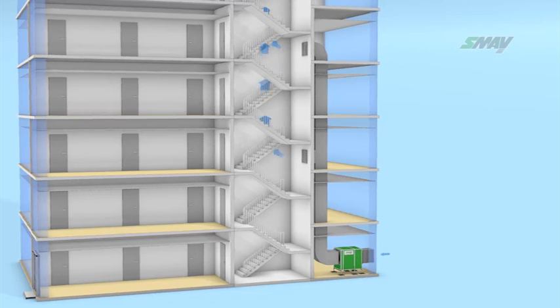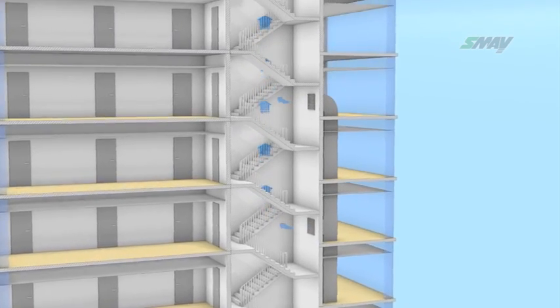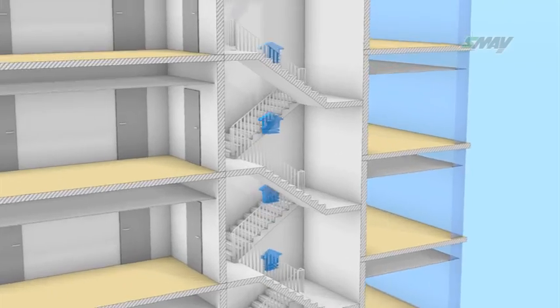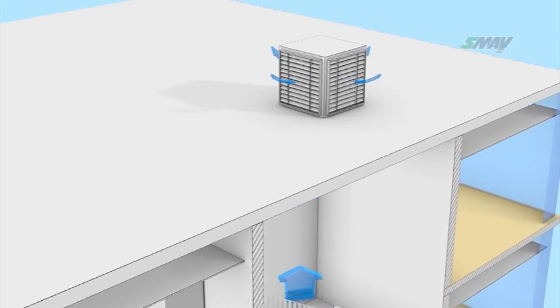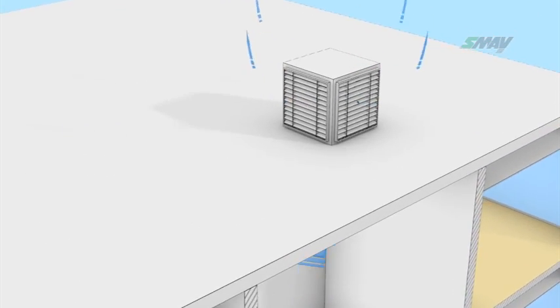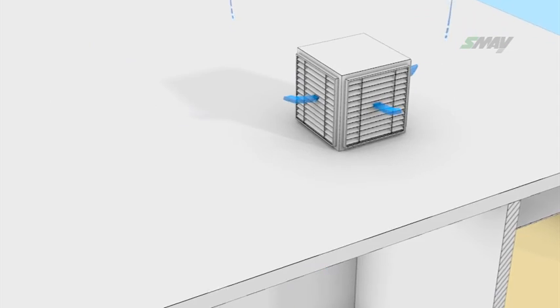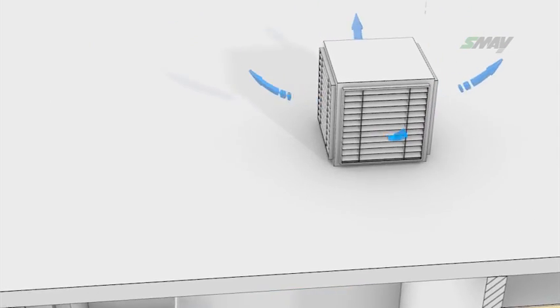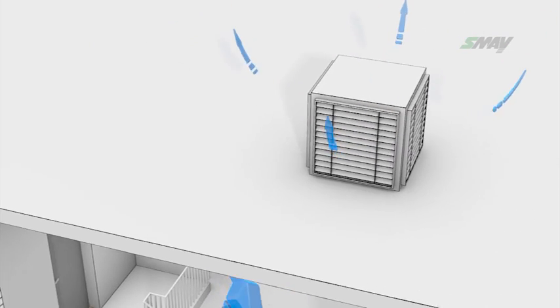In pressure differential systems designed with a long time delay from the fire detection moment to the activation of the system, it is recommended to provide an opening at the top of the staircase with an active area of 0.3 square meters.